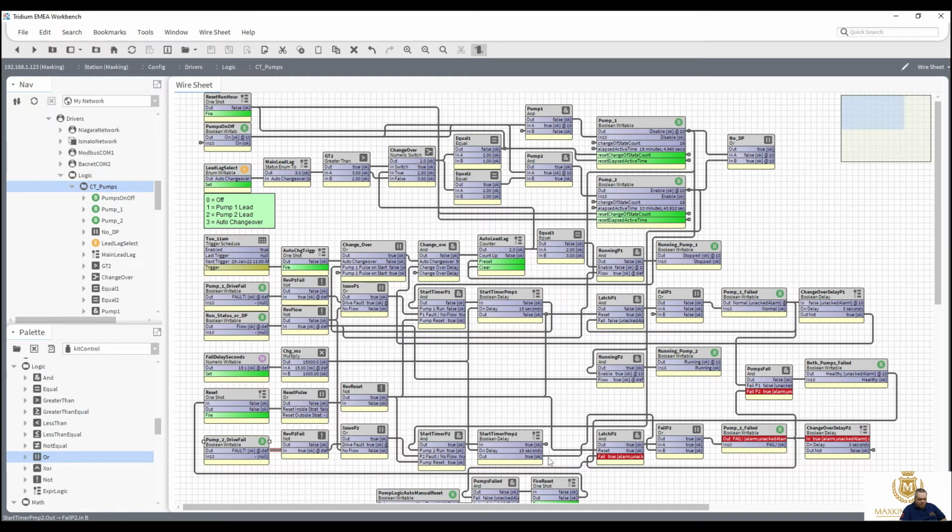We've got a P2 alarm. So why didn't we get the alarm when pump 1 was in fault? Because it's not asking for it. Let's just take that out. And we'll take the 1 out of that one as well. So that's now timing 15 seconds.